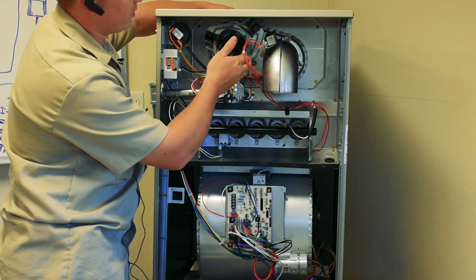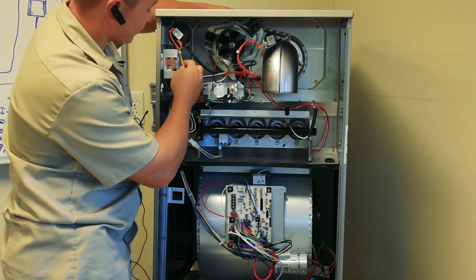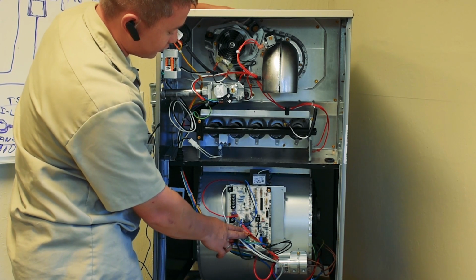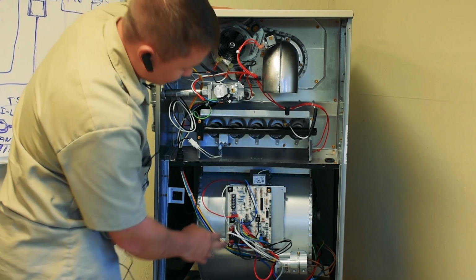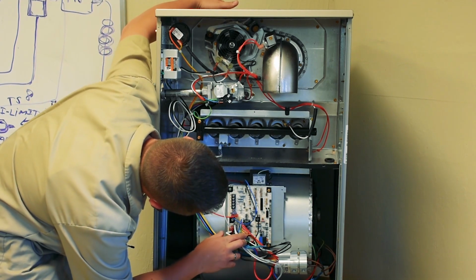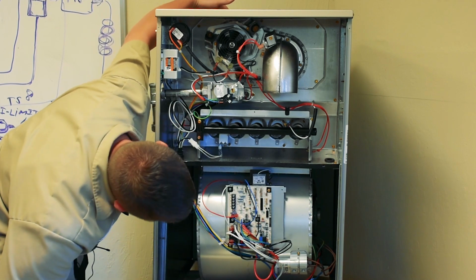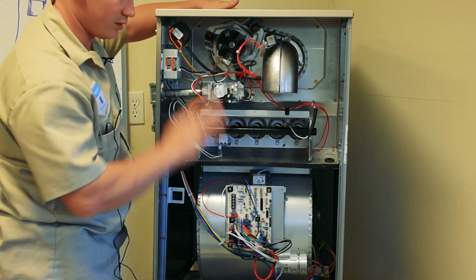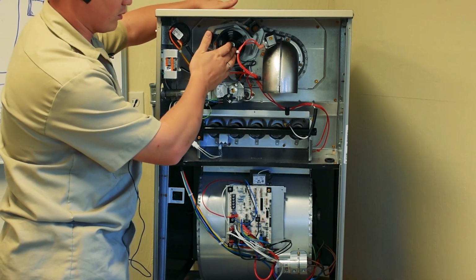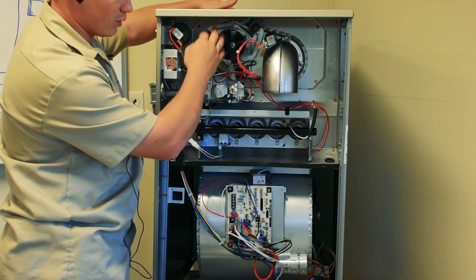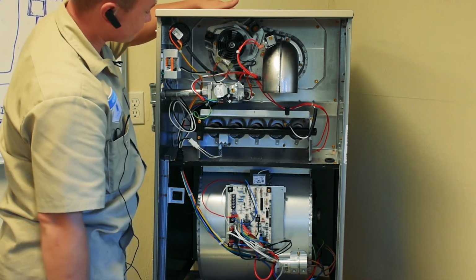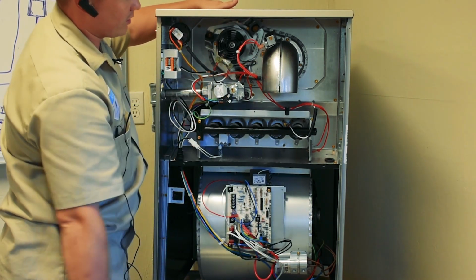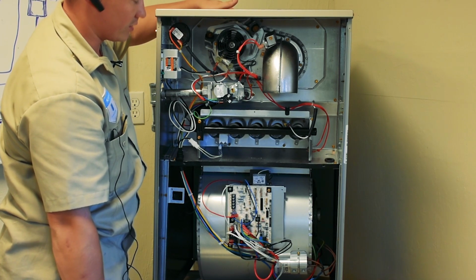It will try to run the inducer motor multiple times, but the circuit for the pressure switch will be off. You will probably also be able to see the issue at the control board. Here I have a small indicator which will tell you what could be wrong, like a pressure switch issue or something like that. In this case, it could be that the blower wheel motor is just not running, or something is wrong with the blower wheel inside this inducer motor, because it couldn't run out the carbon monoxide and carbon dioxide.